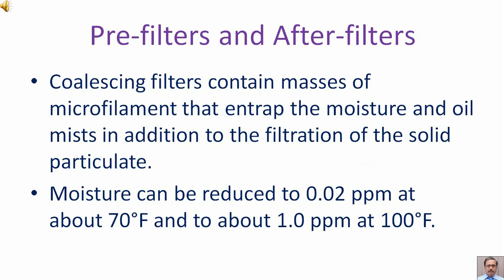Coalescing filters contain masses of micro-filament that entrap moisture and oil mist, in addition to filtration of solid particulate. Moisture can be reduced to 0.02 ppm at about 70°F and to about 1.0 ppm at 100°F.